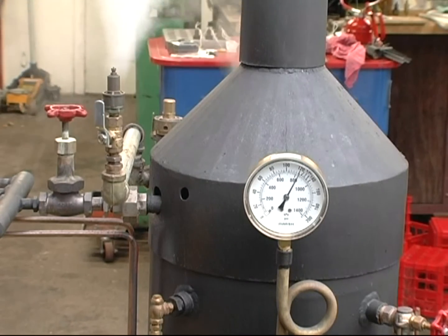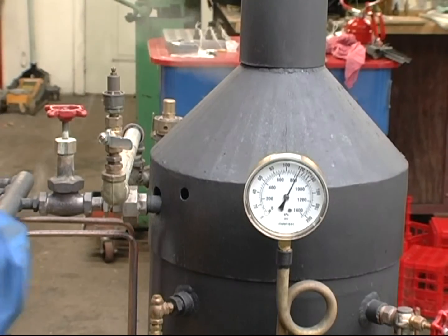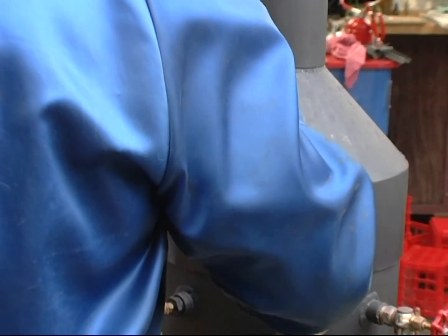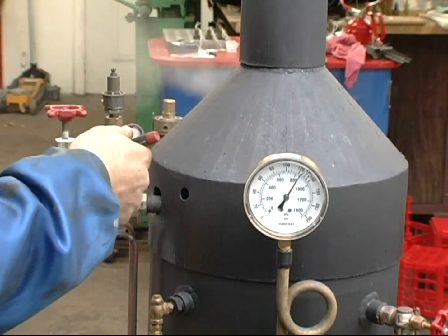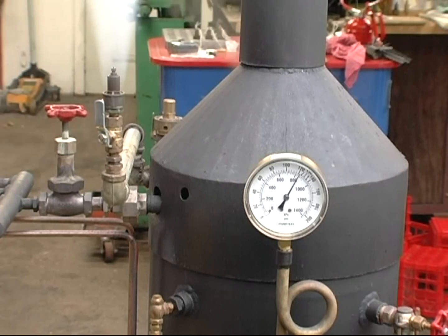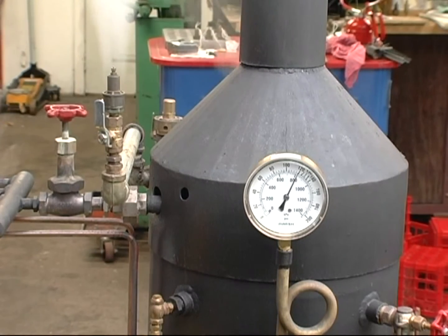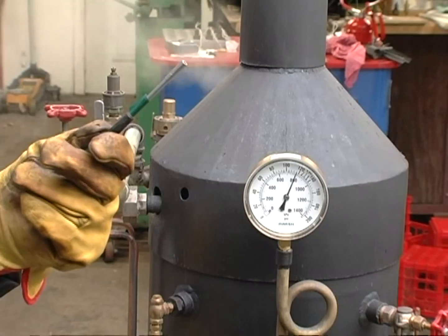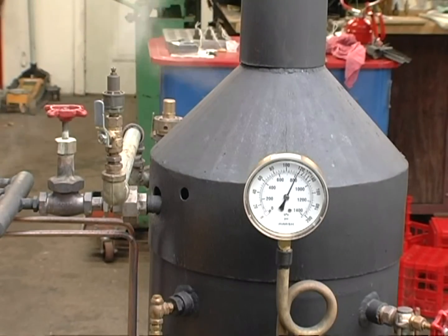This is the second to last one I need to do. Still not the way I like it. We're going to raise it up two notches. I put a little mark on the blowdown ring so I can see where I'm at. On the new ones, I've got the little set screw situated right over a rib — I'm going to move it over here so I can look straight into it and set it a little bit better. The V goes into the notch and just stops it from turning; it doesn't really put pressure on it, because if it did, that would set it off a little bit. I'm using a 1-72 screw for the set screw — it's a 7/64ths Whitworth and a little square-head screwdriver.